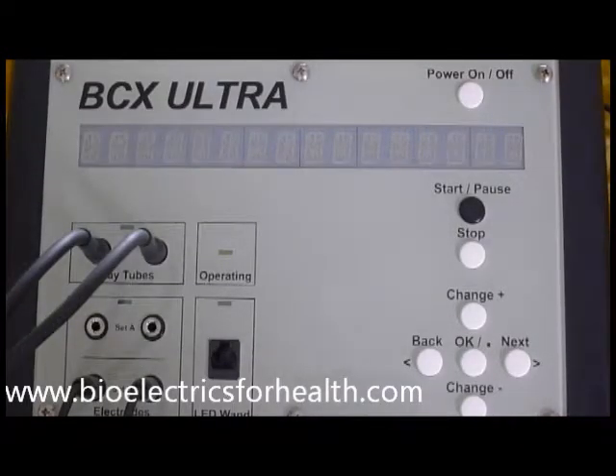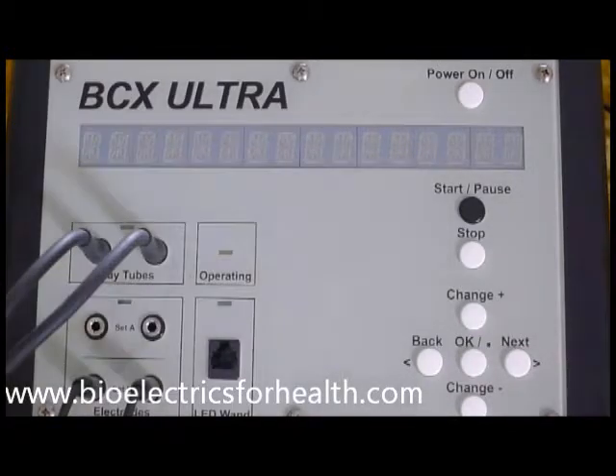Part 2: Running a pre-stored program. Choose a pre-stored program number from the frequency and procedural guide. Note the boldface program number on the left margin, followed by a group of frequencies. These frequencies have been pre-programmed into the BCX Ultra. You will only need to enter the boldface program number. For demonstration purposes, I will select program number 35.